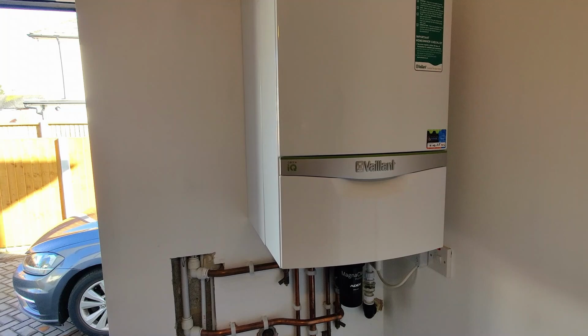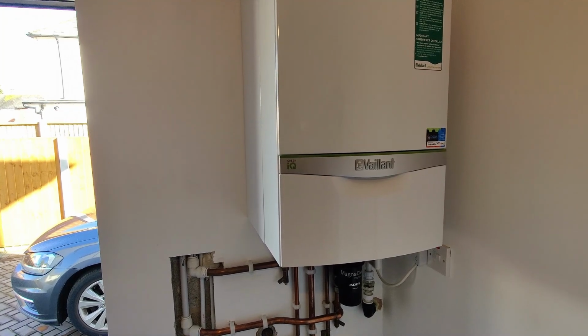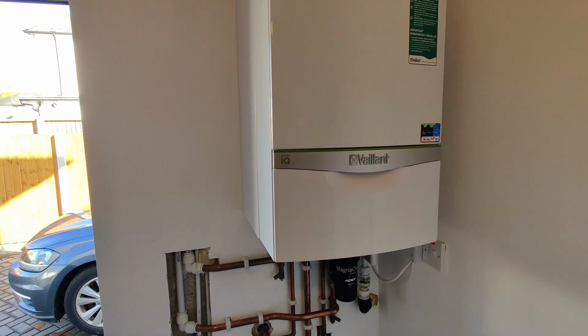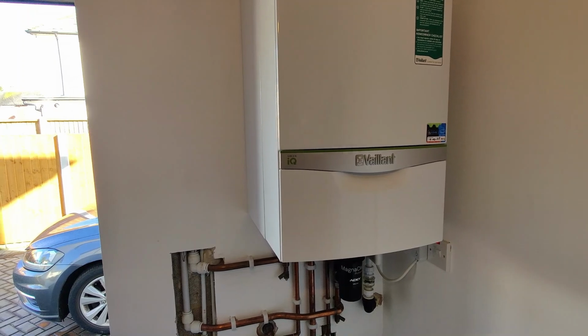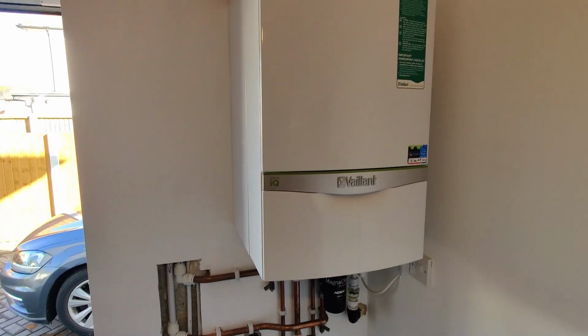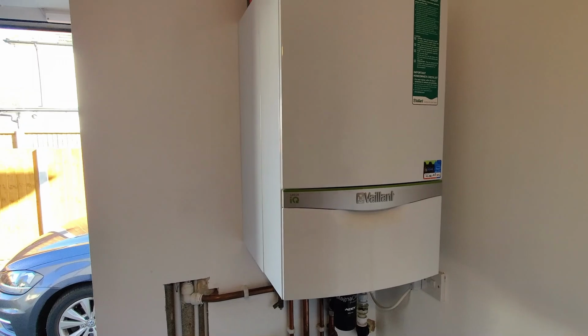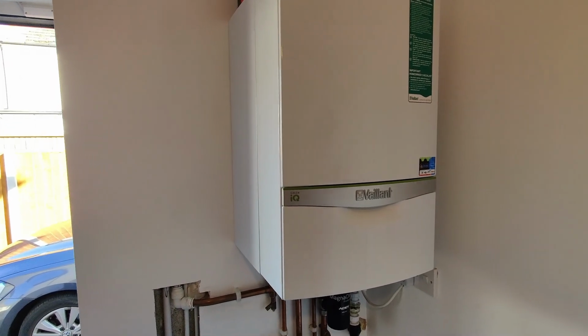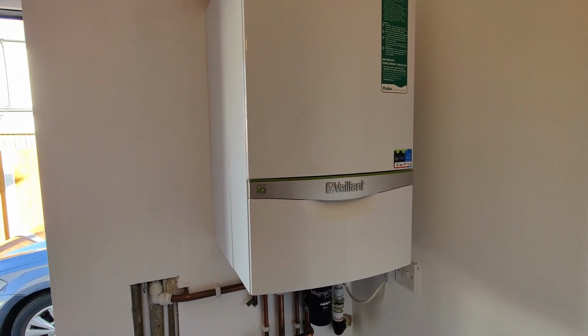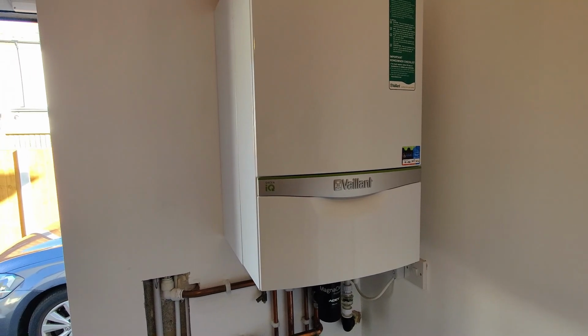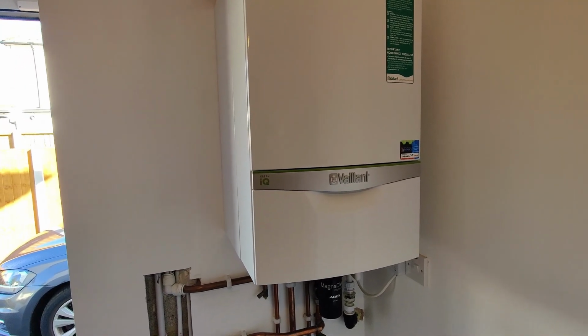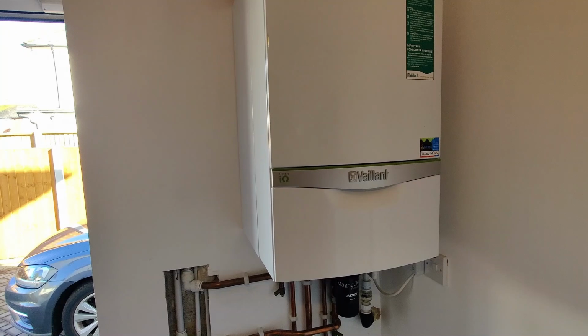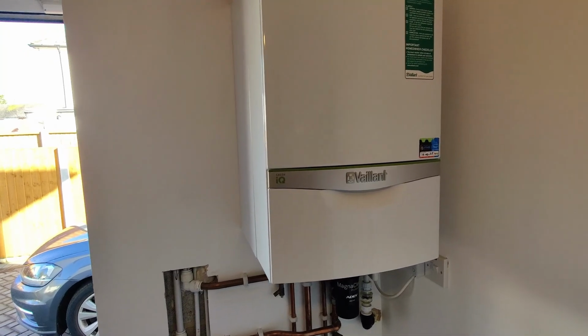And what happened to this particular boiler is, a year later or 6-7 months later, the main heat exchanger for some reason got blocked. So there was a warranty call and I think there was something wrong with that heat exchanger. So Vaillant came out and they changed the heat exchanger at that time. So the heat exchanger is a year and a half old possibly. So that's the reason I've not opened it up on this occasion to clean it out internally. It's brand new, near enough.